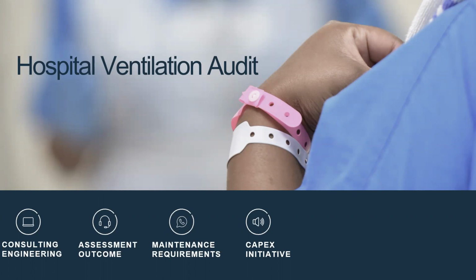So once we have all conducted this, there is only one tool that would typically assist us in proving this from a facilities management point of view on site, as a snapshot of what our systems are doing and capable of doing, and that is by means of carbon dioxide monitoring. So you have a special handheld device that we are using at the moment, and you can also buy equipment that you can fix against the wall, install in ducting units of ventilation, mechanical ventilation systems to actually provide you with carbon dioxide quantification that's measured in parts per million.